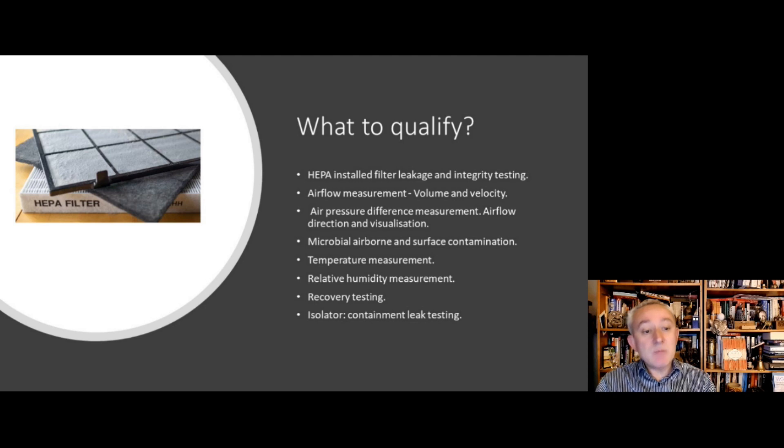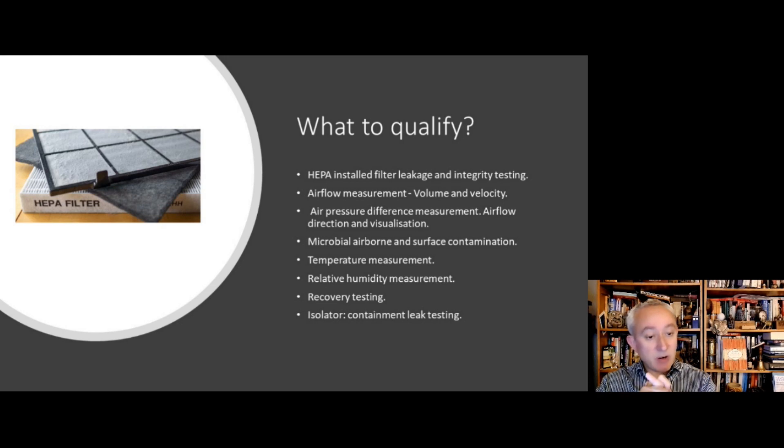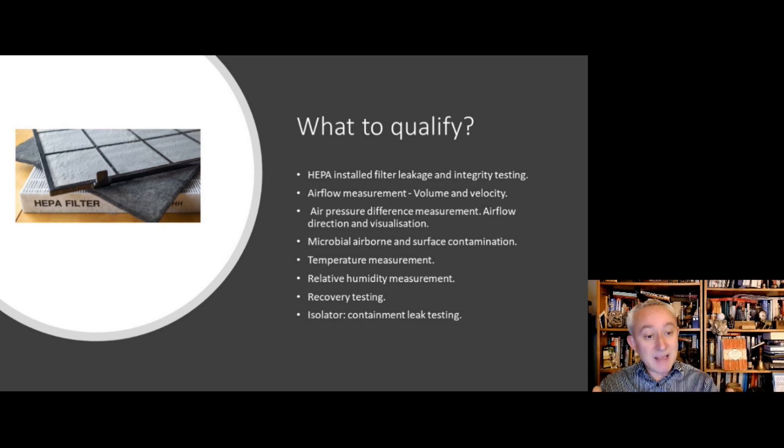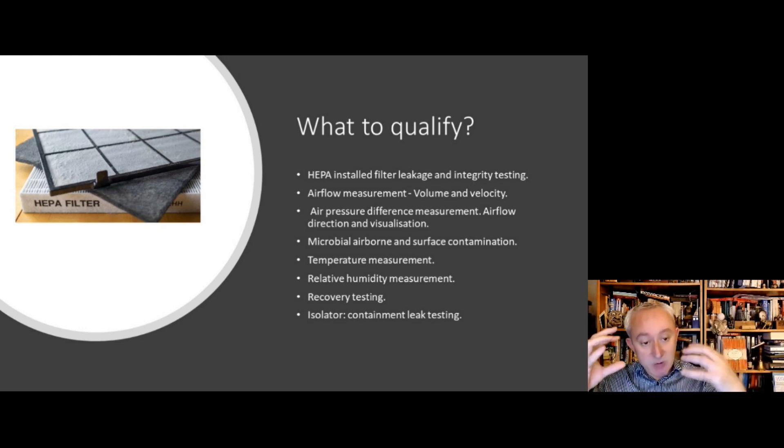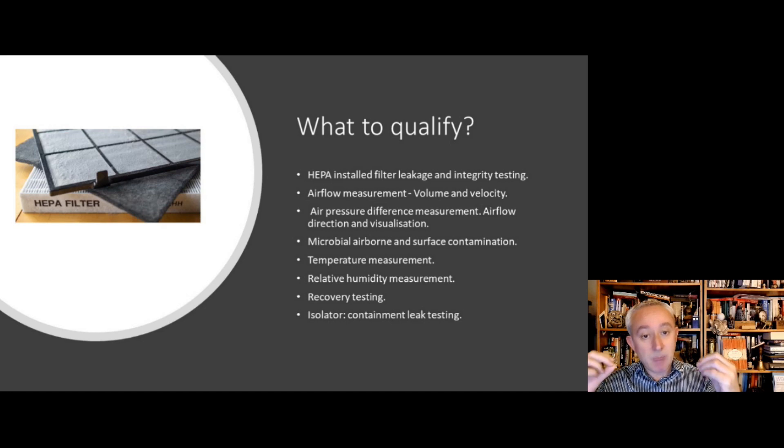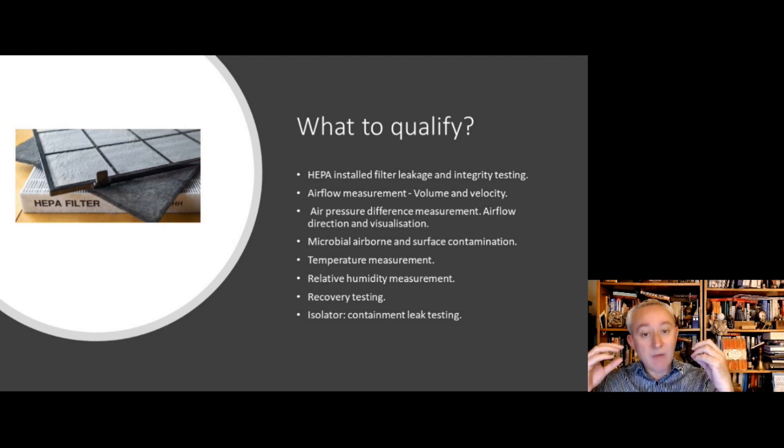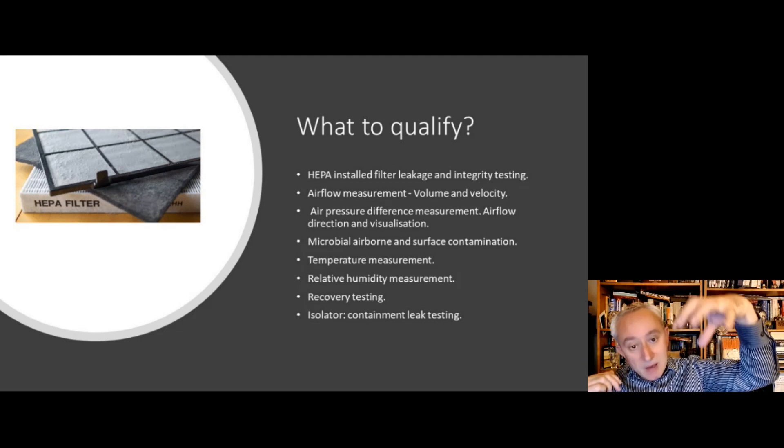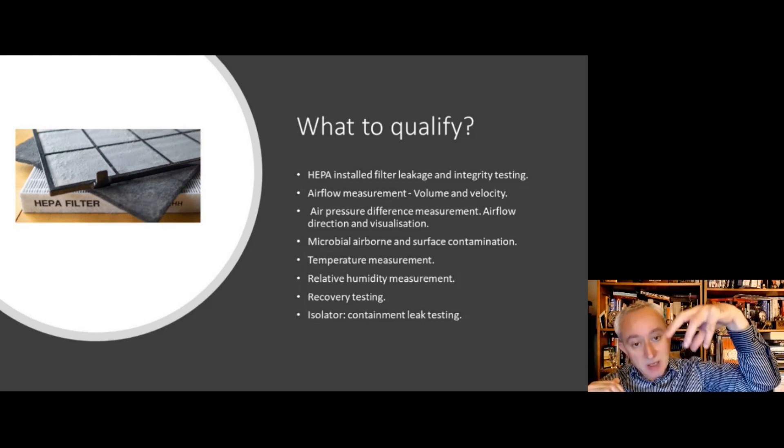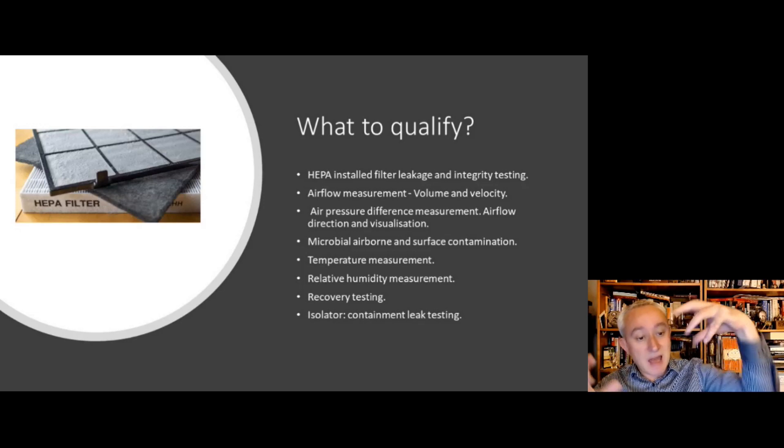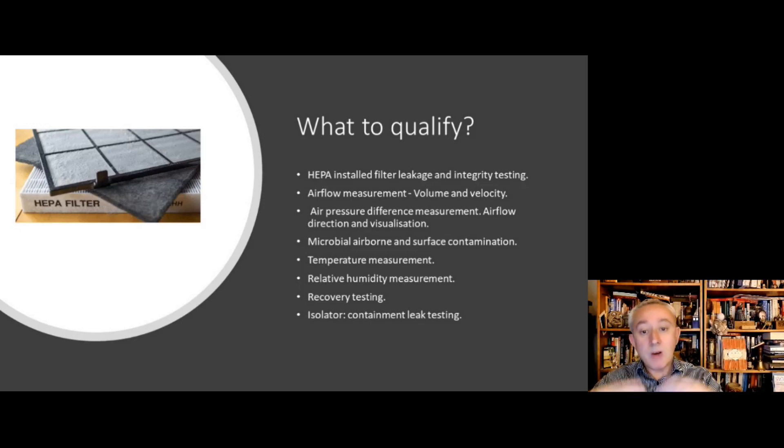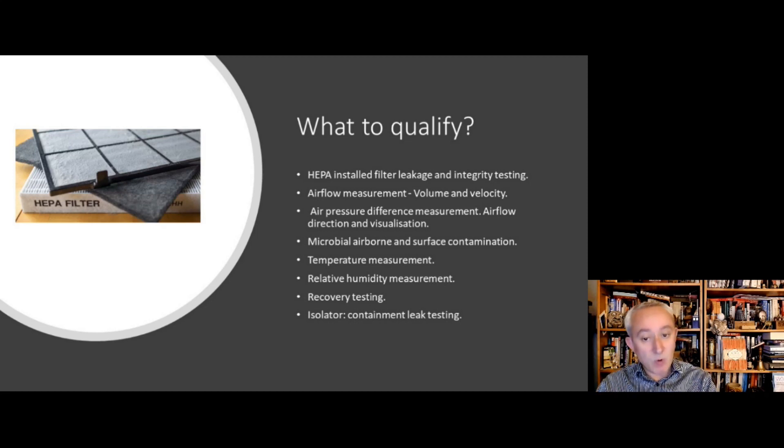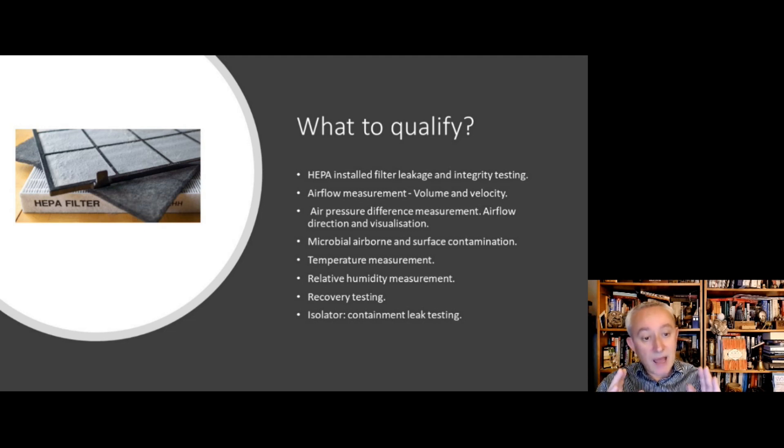In terms of what to qualify, the Annex is saying that you need to ensure that HEPA filters are functioning correctly and have been installed correctly. So that's about filter leakage testing, and as we found out last time, that's not just the HEPA filter media but all the surrounds and seals and so on around the filter. Also, to assess the filter integrity by integrity testing, we need to understand the airflow measurement—that's the volume of air coming into the room and the velocity that is coming into the room, and that links to the air change rates as well. We need to understand the air pressure difference, particularly between two different rooms, and we need to have an understanding within every clean room of the airflow direction and an idea of the route the air is taking through a visualization study.